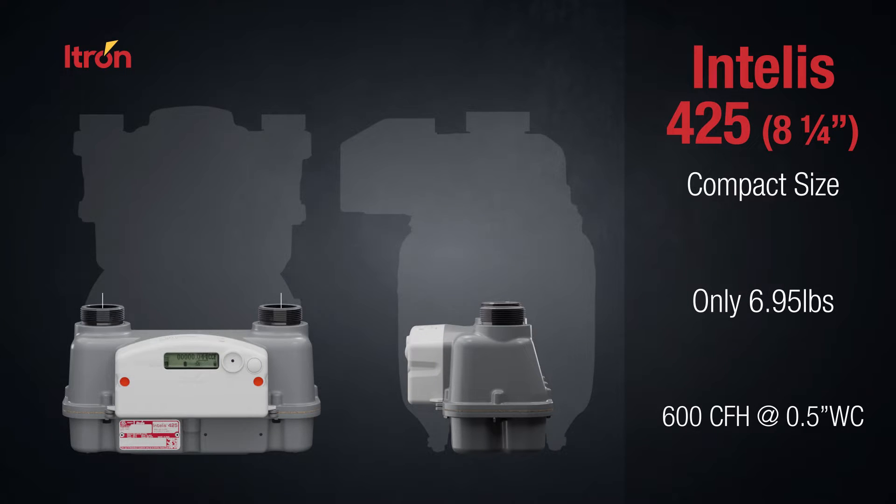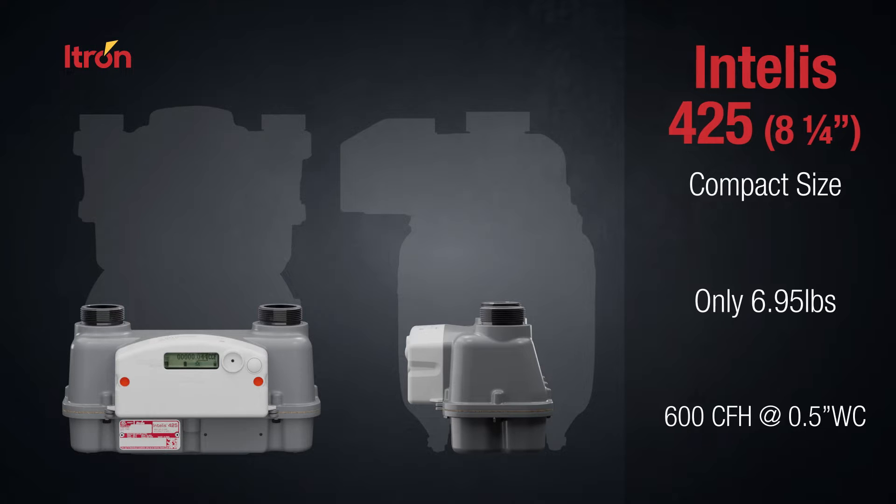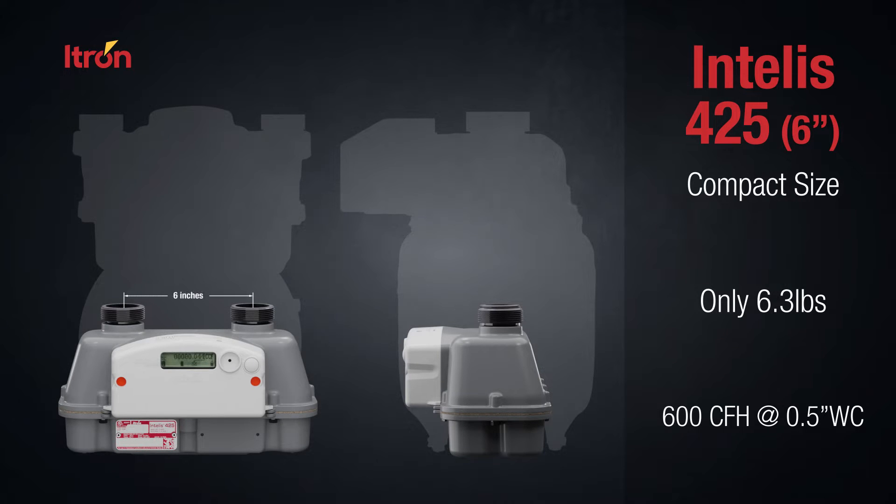The INTELIS 425 gas meter is a compact ANSI 500 class meter with an impressive capacity of 600 cubic feet per hour at a half-inch water column, available with both an 8 and a quarter and 6 inch hub center to center distance for easy field retrofits.